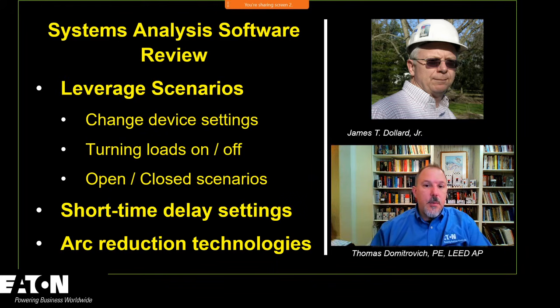or you can put a fusible disconnect switch in front of something and help you reduce the incident energy and create a lower impact for the electrical worker. You can run these different scenarios that can give you a picture of a design change or a system change. If I turn a lot of motors off, I can lower fault contribution to a point where I'm in a longer time region clearing time, and that could create a higher incident energy than if I had all my motors on. And it's good to be aware of that.